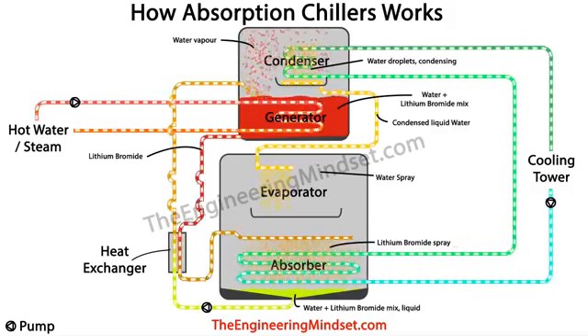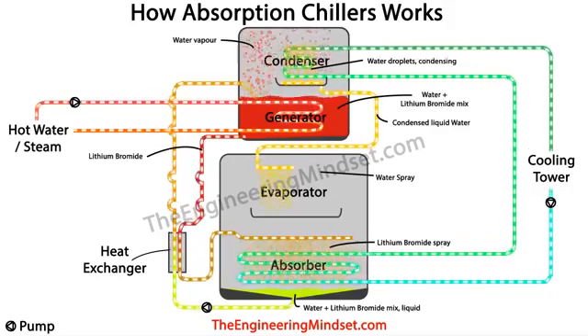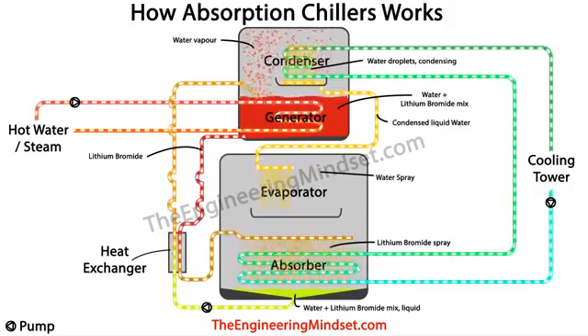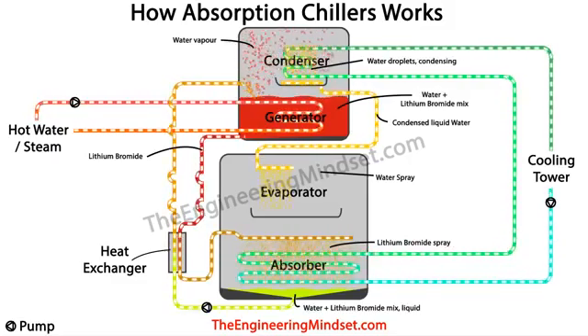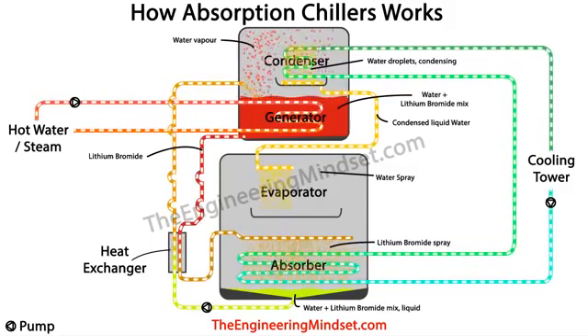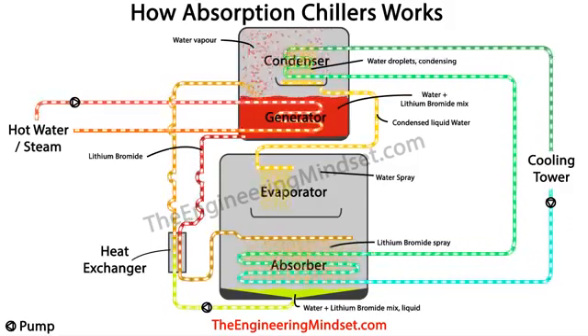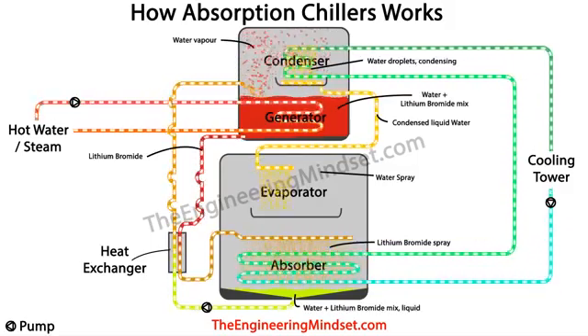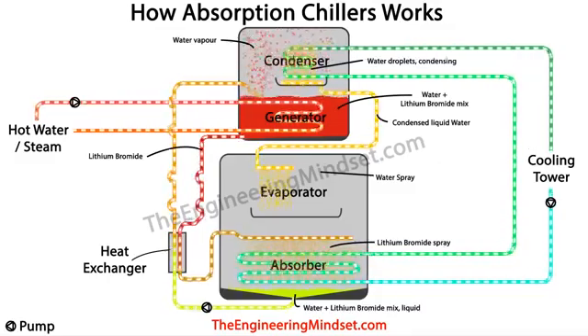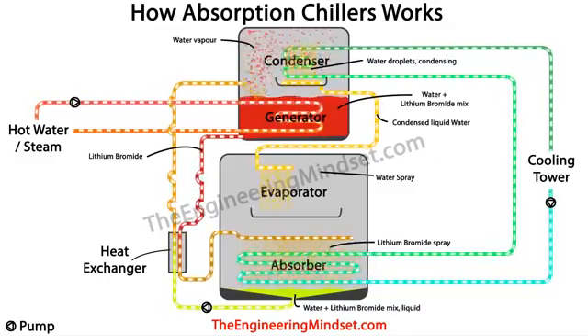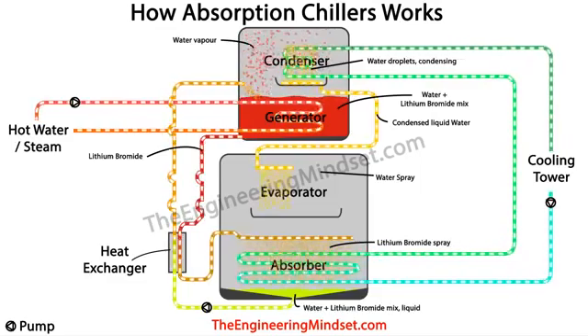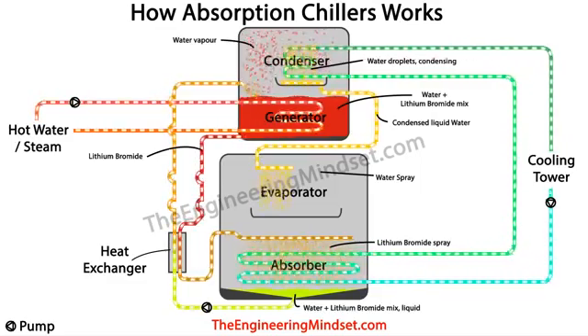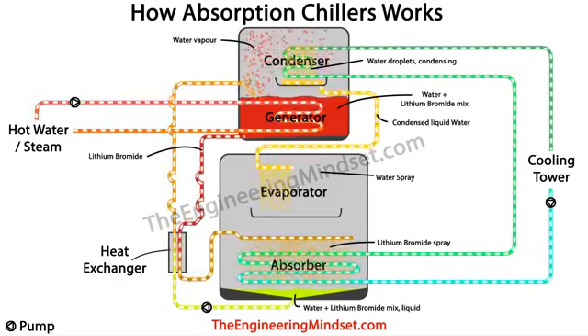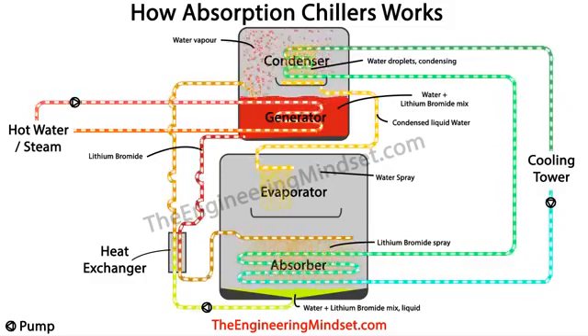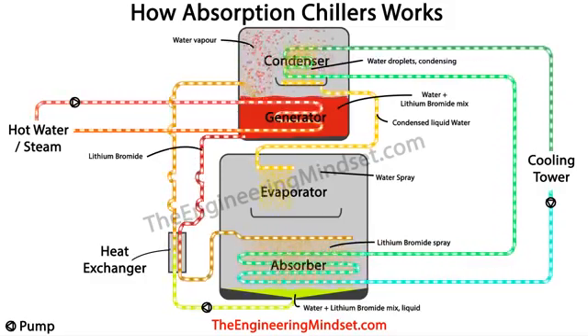Once it collects in the tray, it will start to flow down to the evaporator and will be sprayed into the chamber. The amount of water that can flow is restricted by a small orifice in this pipe. Now the evaporator, as we mentioned earlier, is at a very low pressure. It's almost near a vacuum condition. Now this sudden change in pressure will cause that water that's entering to suddenly flash and drop in temperature into a cold water of around just 4 degrees Celsius, maybe 40 degrees Fahrenheit.